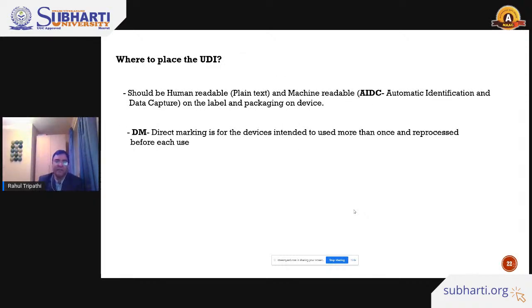Where to place the UDI? It should be human readable, so it should be readable either by human or by machine. So it should be AIDC, automated identification, which you can capture easily using a barcode machine. So that needs to be put on the label or on the package of the medical devices.